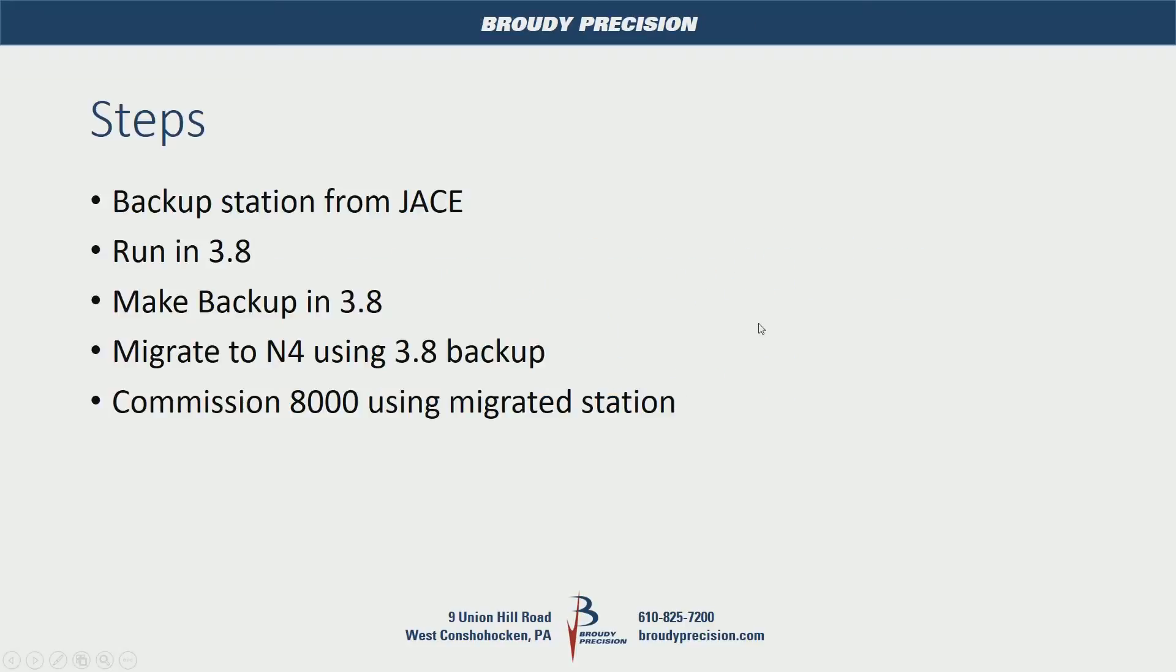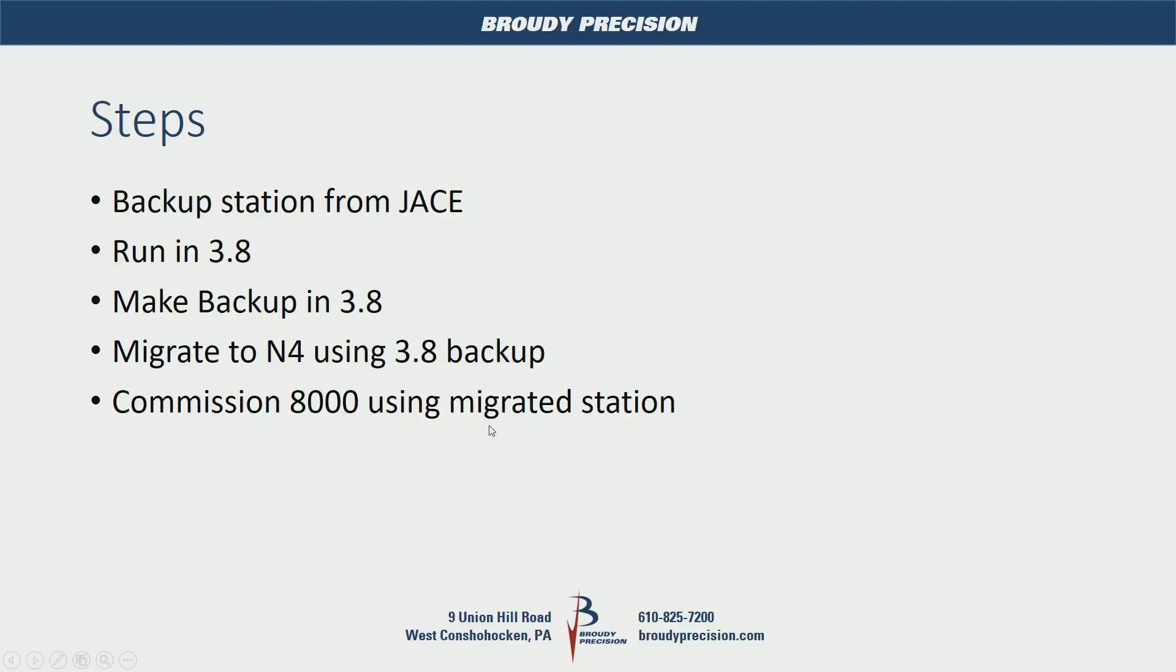So before we get started, here's our steps. First we're going to pull a backup out of the existing Jace, then we'll crack that backup open, we'll run it in 3.8, we'll make a backup in 3.8 running on our local machine so that we can run the migration utility to get that station up to Niagara 4, and then we'll commission our 8000 using that migrated station.